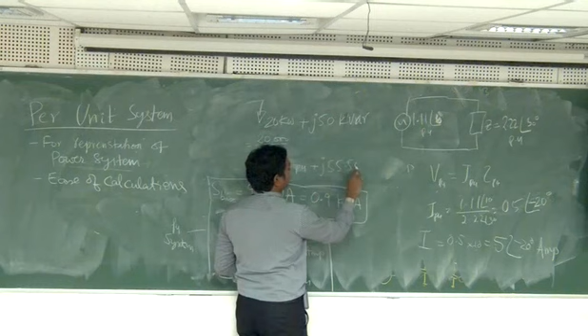To cancel out kilowatts, you can divide by this VA itself, you can cancel out that. So this is 20,000 divided by 900. How much is this? 22.22 per unit, plus j 50,000 divided by 900. How much is that? 55.55. Interesting. So this is again in per unit.